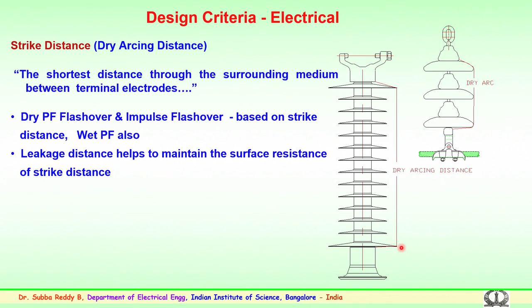So, the leakage distance I pointed out, again here the dry arcing distance which we discussed, is from the electrode of the high voltage to the electrode of the ground side. The leakage distance basically is the sum of the shortest distances measured along the insulating surfaces. You can see the leakage distance, again I stress here, from the pin of the third insulator, it goes through the creepage of the entire insulator and comes here near the cap.